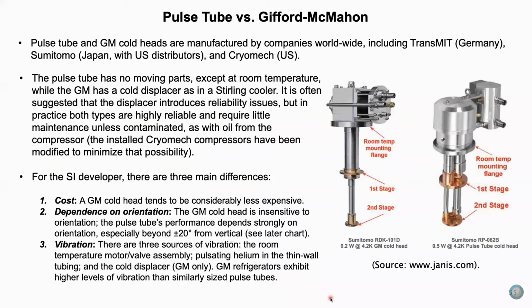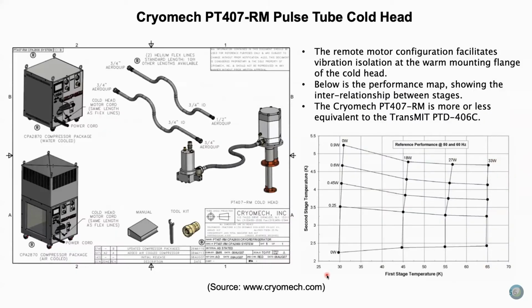And finally, there's vibration. There are three sources of vibration: the room temperature motor and valve assembly, pulsating helium in the thin wall tubing, and the cold displacer. That's for the GM only. The pulse tube doesn't have a cold displacer. GM refrigerators exhibit higher levels of vibration than similarly sized pulse tubes. So it's for this third reason that pulse tubes generally are used for low temperature work, that is, as a stage for other low temperature stages. But the GM should not be dismissed out of hand just because there is this belief that it's much noisier. It's not that much noisier.